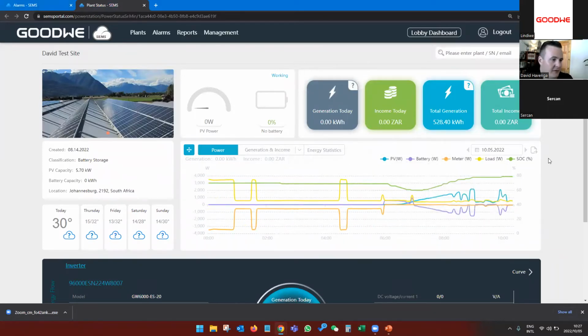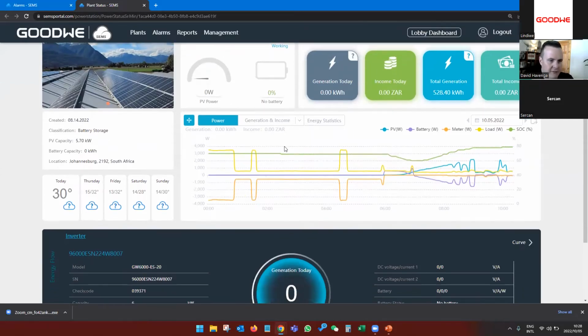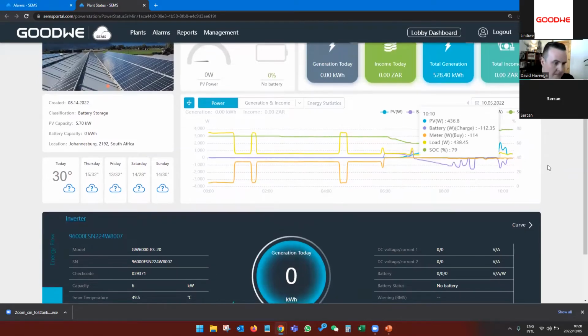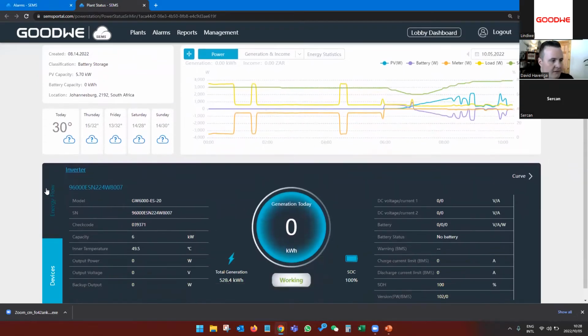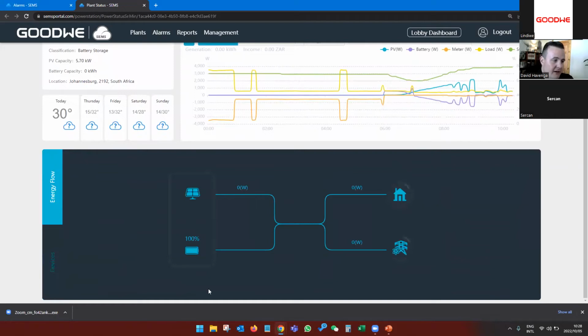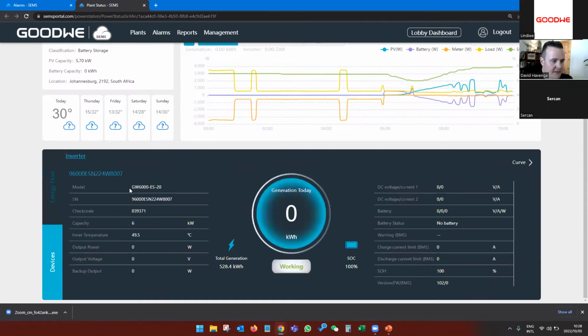Here we can do some fault finding. We can see how the inverter is working. We can see the operating mode. We can see our batteries as well as the percentage of the batteries. Currently, the system is a bit offline, so it's not showing us the correct information. First of all, we'll have our energy flow diagram here and the devices tab. In the devices tab here, we can see a lot of information: the model, the serial number. We can see the capacity of the system that we put in, so the inverter's capacity, unlike the PV capacity here on top.